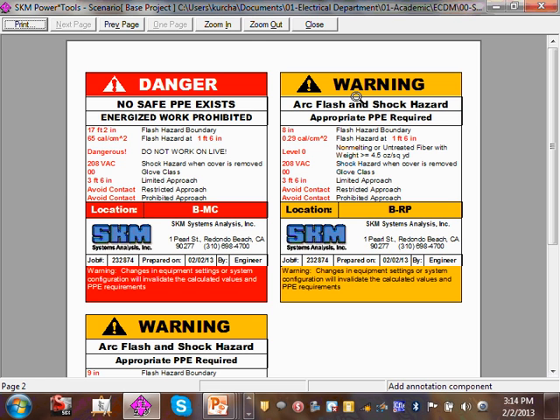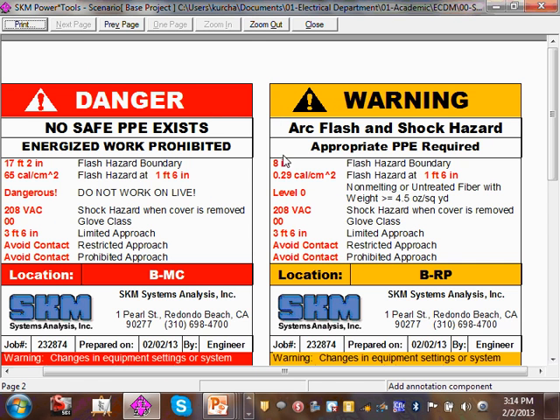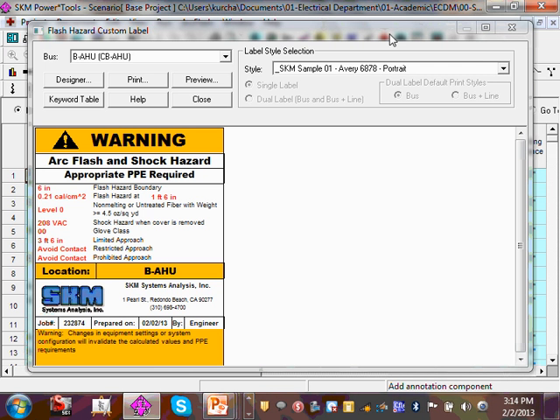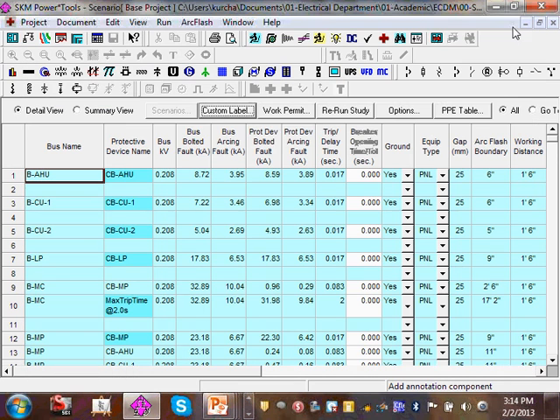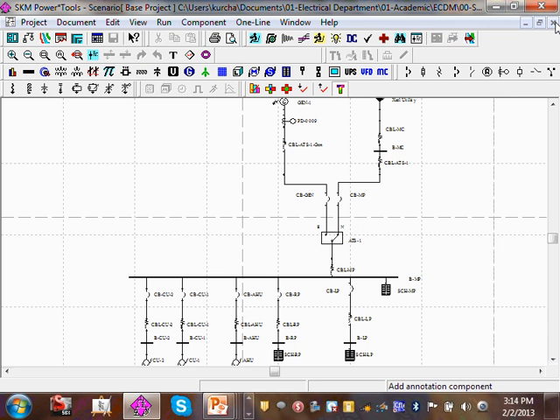Okay, so that's my arc flash. So I thought to show you guys, not bragging or anything. A lot of people do that. So you start by building your one-line diagram from the components. You run short circuit analysis. It gives you the short circuit level in every switchgear or panel, and then it gives you labels too. The arc flash label that you can stick right onto your panel.